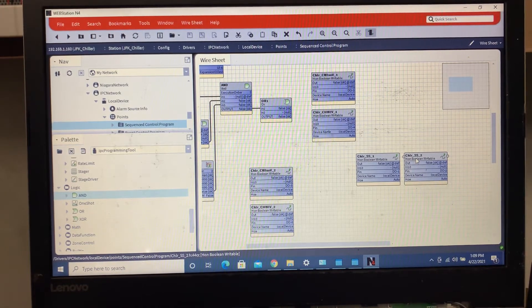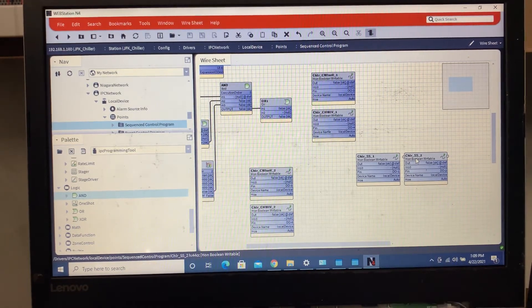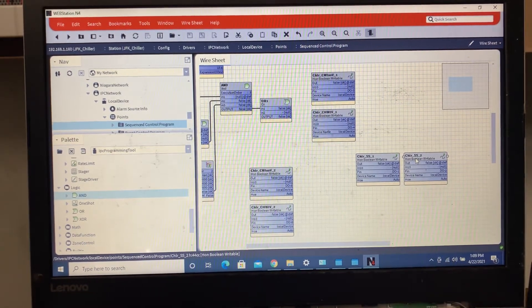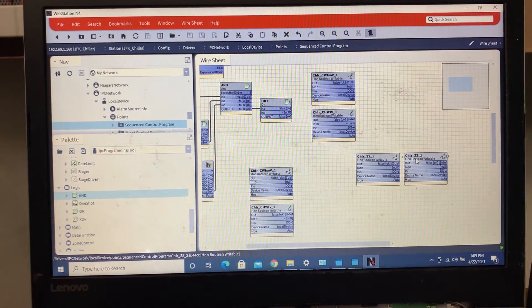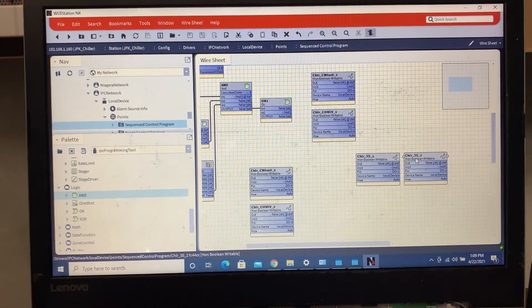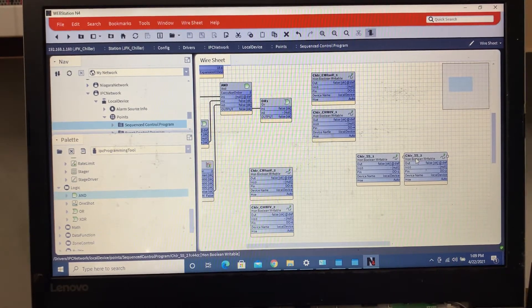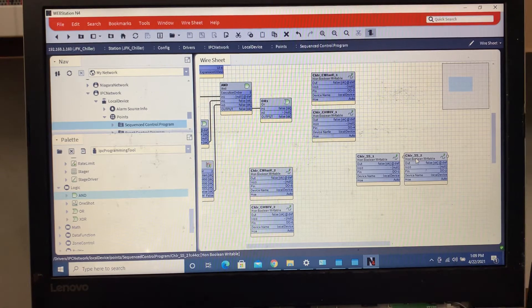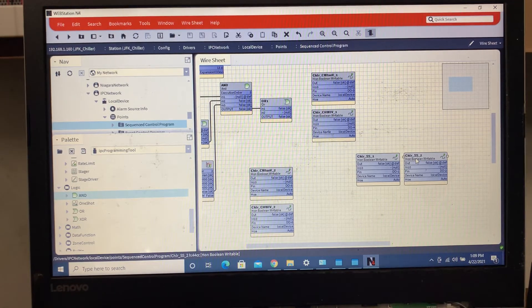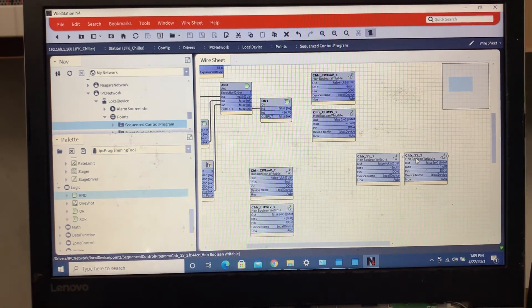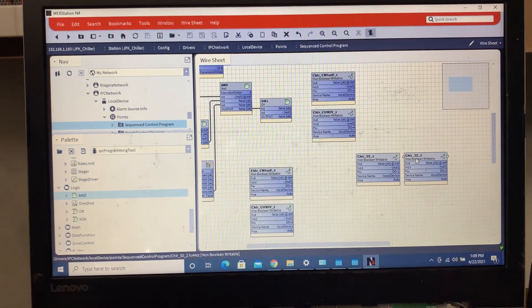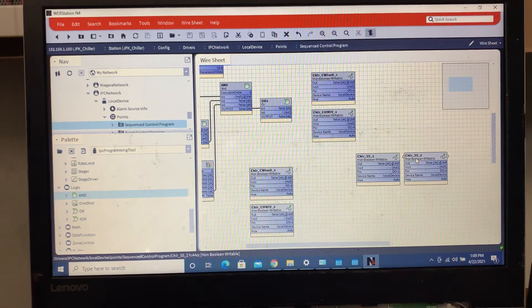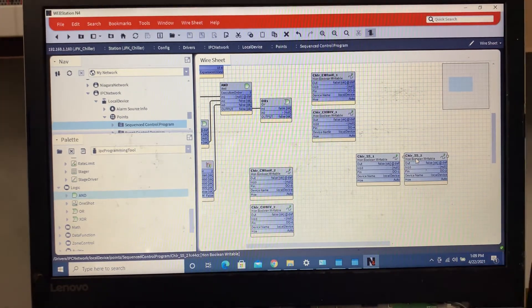Or you got the ones where if you got mag bearing chillers, you can do once the chiller gets up to about 80 percent full load you start bringing the other chiller on, so that way it drops the load.